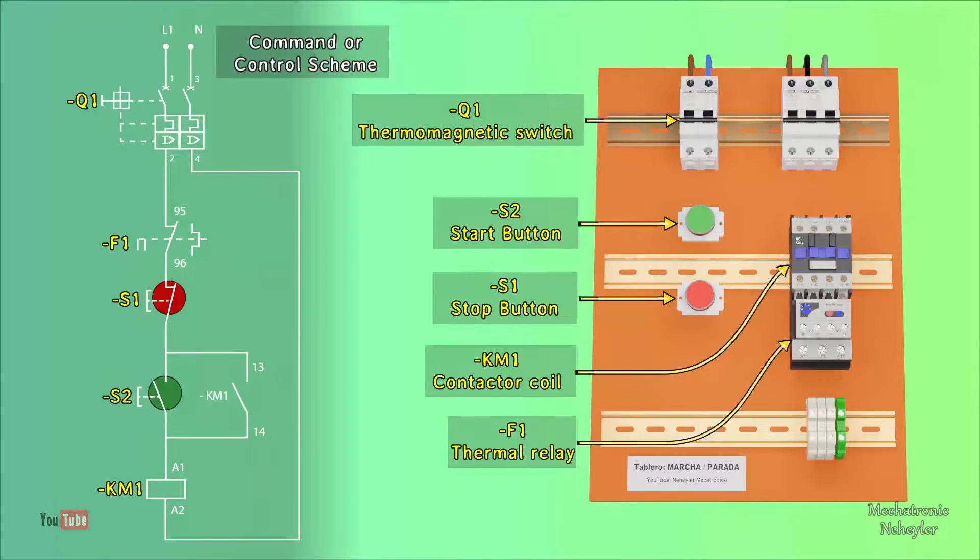KM1 corresponds to the supply that must be made in the contactor coil, as well as for its self-holding. F1 corresponds to the thermal relay, which fulfills the function of protecting the motor against a possible overload or overheating in the motor winding.